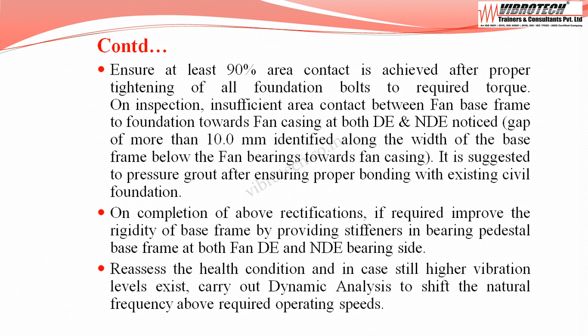On completion of the above rectifications, if required, improve the rigidity of the base frame by providing stiffeners in the bearing pedestal base frame at both fan DE and NDE bearing side. Reassess the health condition, and in case still higher vibration levels exist, carry out dynamic analysis to shift the natural frequency above required operating speeds.